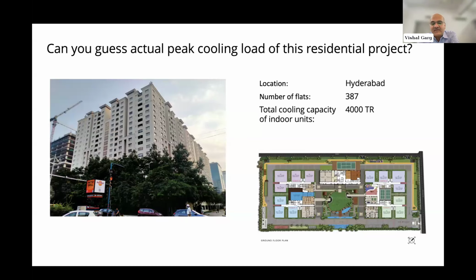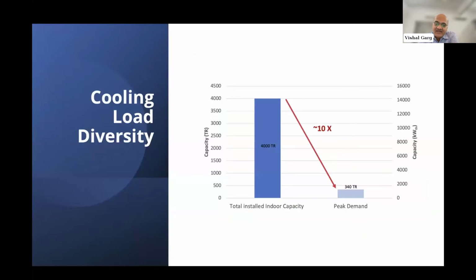In conventional case, if it would have been split air conditioners, for every ton of indoor unit, there would be a ton of outdoor unit. So that means it would have required 4,000 tons of compressing power. But in case of aggregated load, to our surprise, instead of 4,000 tons, the requirement was less than 400 tons. So there is a substantial reduction in our installed capacity. And this is very obvious once we analyze this data.